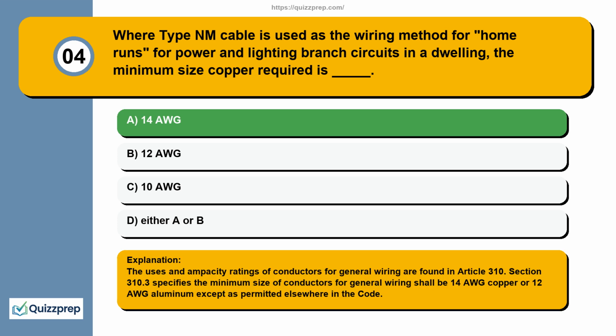The uses and ampacity ratings of conductors for general wiring are found in Article 310. Section 310.3 specifies the minimum size of conductors for general wiring shall be 14 AWG copper or 12 AWG aluminum, except as permitted elsewhere in the Code.